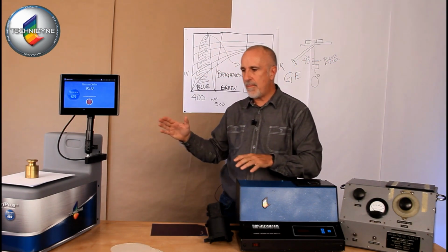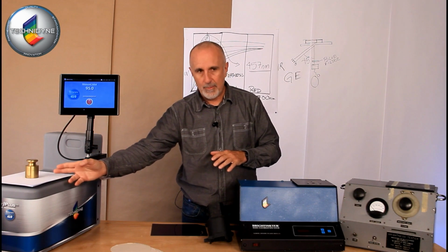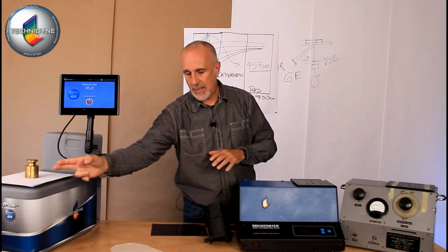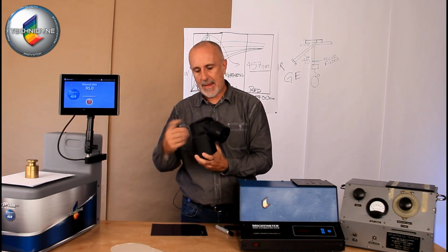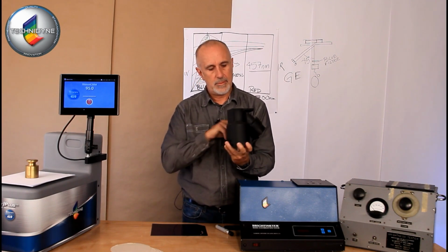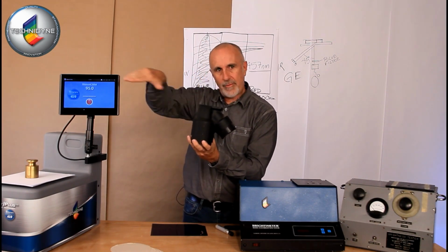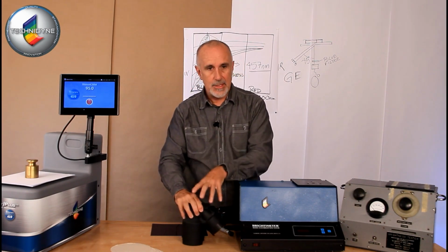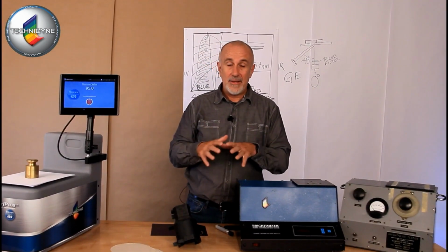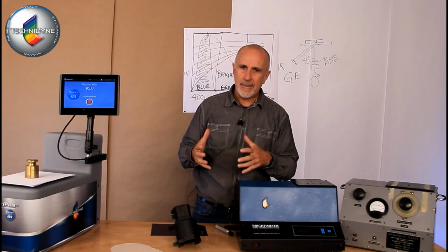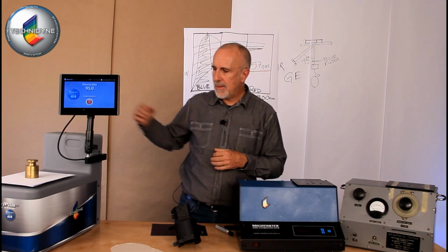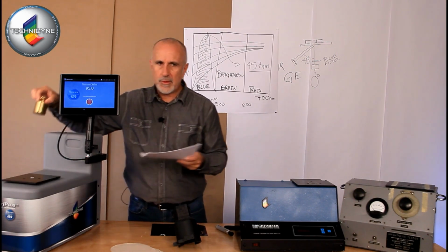Okay. So you always want to measure machine-made paper in the orientation of the fiber to line up the light angle. In this case, light angle with the fiber angle, okay, because this geometry is susceptible to the fiber orientation. In addition to the fiber orientation, there are a couple other things you need to keep in mind as you're making brightness measurements. The methods call for the use of an infinite pad.